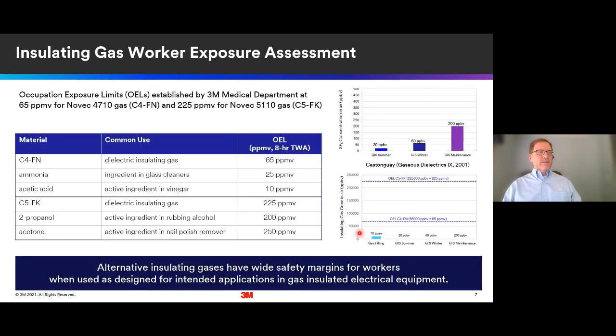So again, based on that full range of toxicity tests, the medical department set the occupational exposure limit, or the OEL, for the C4 nitrile, the Novec 4710 gas, at 65 parts per million. And in the case of the C5 ketone, Novec 5110 gas, at 225 parts per million. And the table below shows, just for comparison purposes, how that compares to other materials that you might have more familiarity with. In the case of C4 nitrile, the 65 ppm exposure limit is compared to ammonia or acetic acid, which is the active ingredient in vinegar. C5 ketone is compared to rubbing alcohol or acetone, which would be like nail polish remover, that type of material. So it's in the range of materials that people already deal with today in their daily lives.